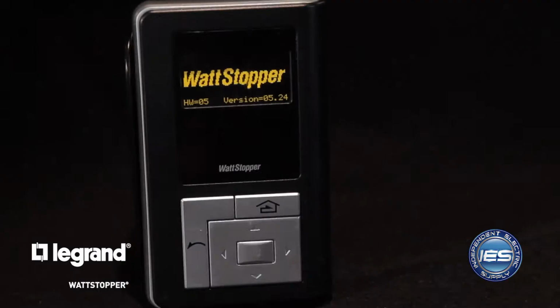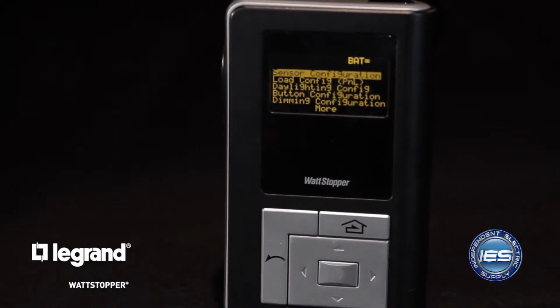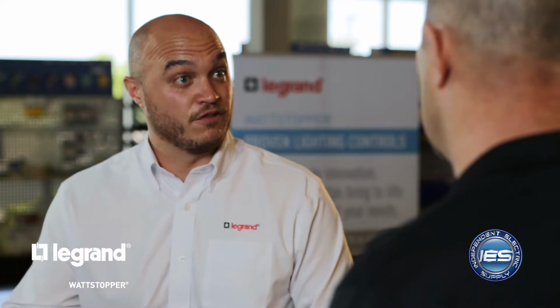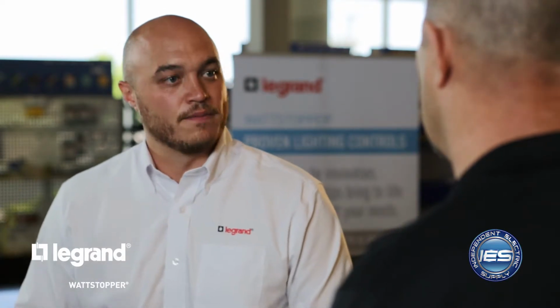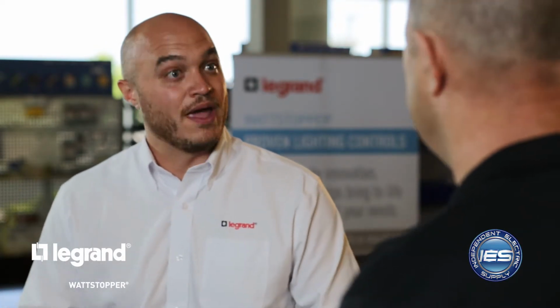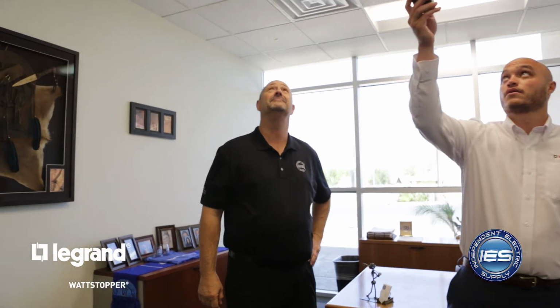What does that mean? Yeah, so load configure is about assigning respective devices to the load. When I enact a load configuration mode, I can then pair devices, maybe a switch or a sensor, to a respective load or loads in that space. If you had multiple switches, you may want switch 1 to control switch leg A, switch 2 to control switch leg B. Load configuration gives you the ability to make those load assignments.